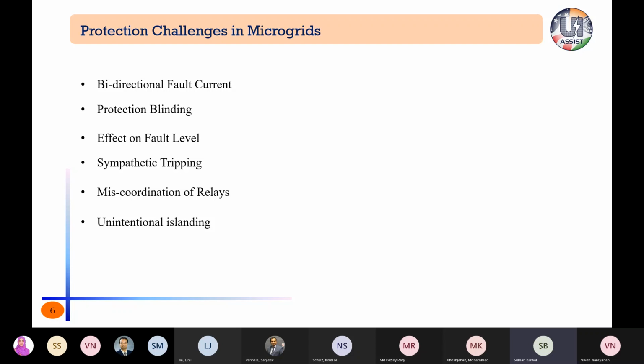Another thing is sympathetic tripping. For this, let us consider an example. We have two feeders, and in one feeder DGs are located. Suppose a fault happens in the adjacent feeder, so that the DGs contribute fault current to that adjacent feeder. It may happen that the DG current exceeds the setting of the relay located nearest to the DG, so it will unnecessarily trip the unfaulted line. This is called sympathetic tripping.